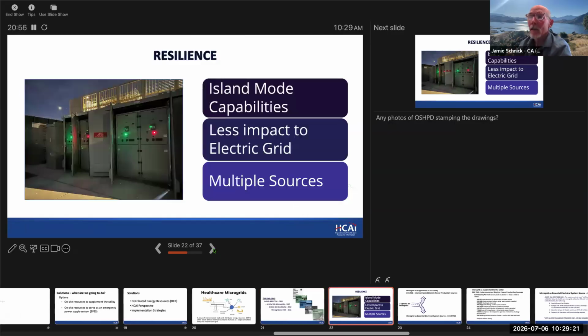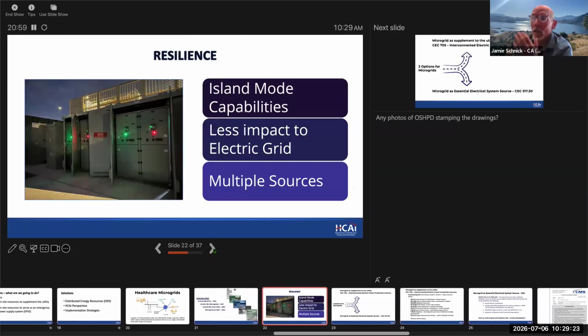The code permits these systems, with great benefits for resilience and hardening your facility through island mode capability. It takes strain off the electric grid by having on-site power generation. Having multiple sources increases reliability, since some sources could continue to operate in the event of a failure of one or more sources.